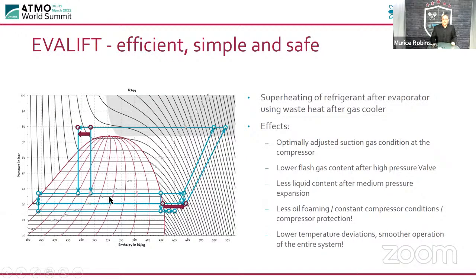So this is what actually happens on the evaporator side. You can see that on the evaporator, we normally have the superheat. So what we're doing is decreasing that superheat down to 0 K. And then we're using that cooling effect on the other side, which is on the gas cooler outlet side, to cool down the gas cooler outlet temperature as well. So you're winning on both sides. So it's an optimally adjusted suction gas condition at the compressor. You have lower flash gas as well after the high pressure valve. There's less liquid content after the medium pressure as well. Lower flash gas and less oil foaming as well.